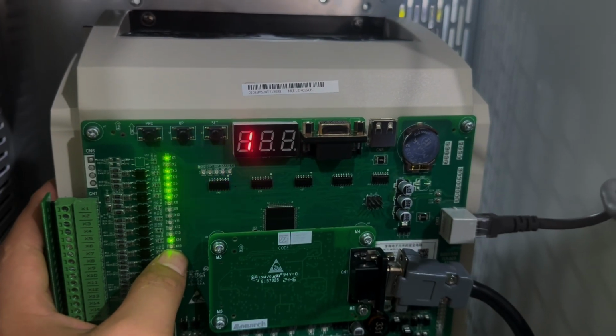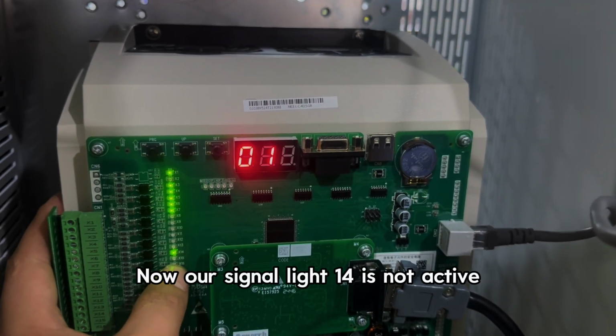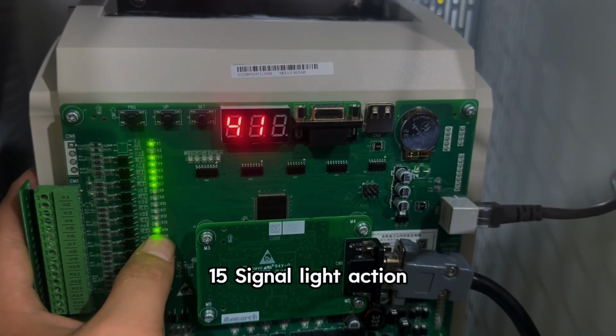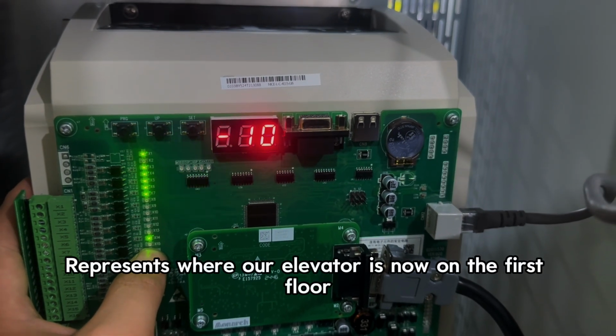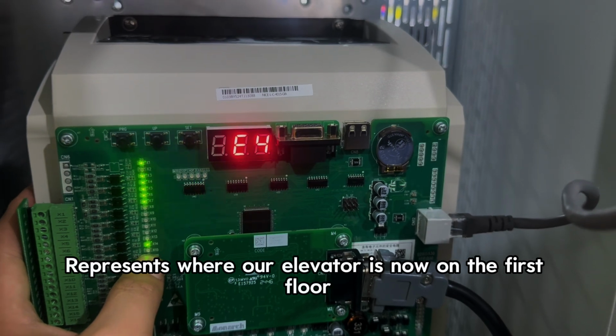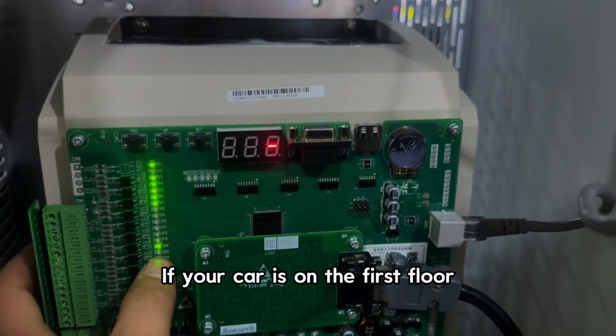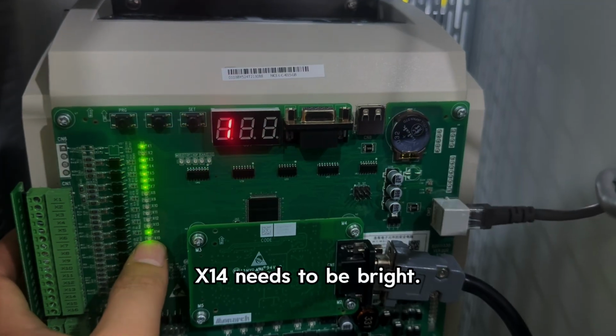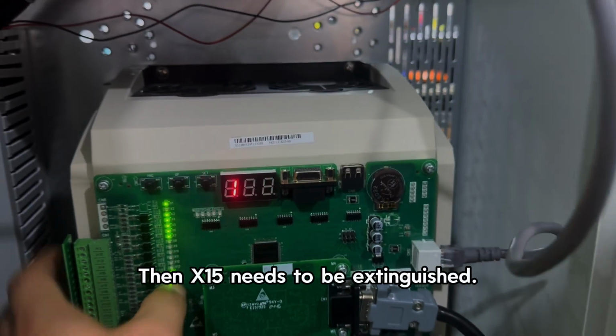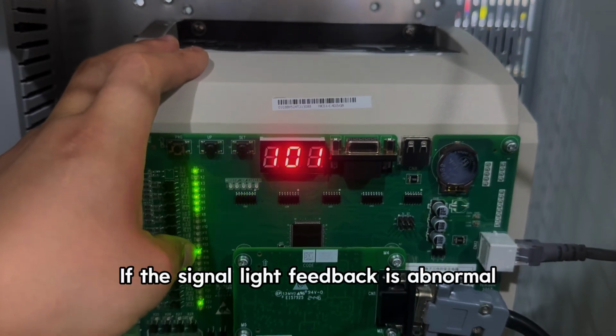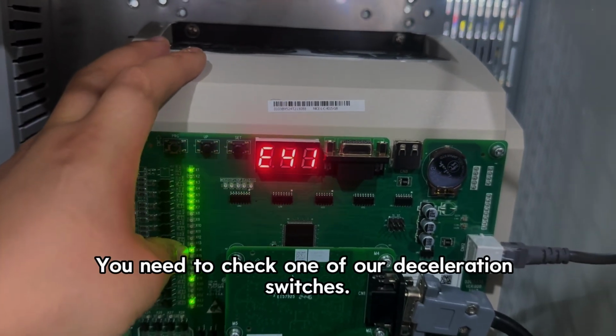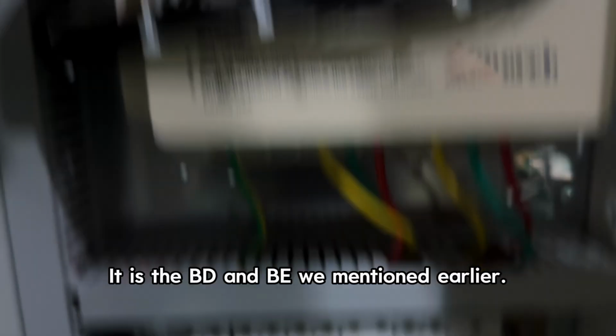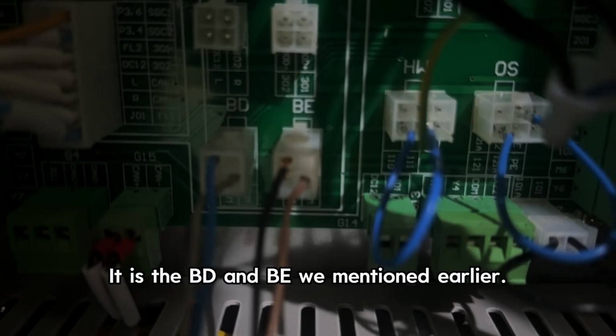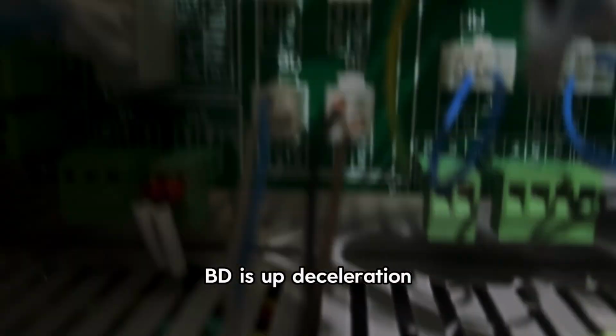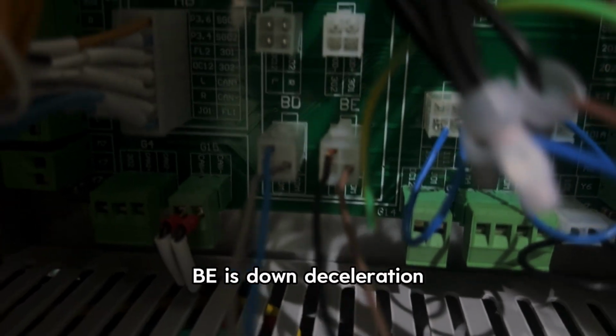15 first. Now, our signal light 14 is not active. 15 signal light action represents where our elevator is now on the first floor. If your car is on the first floor, X14 needs to be bright. Then X15 needs to be extinguished. If the signal light feedback is abnormal, you need to check one of our deceleration switches. It is the BD and BE we mentioned earlier. BD is up deceleration, BE is down deceleration.